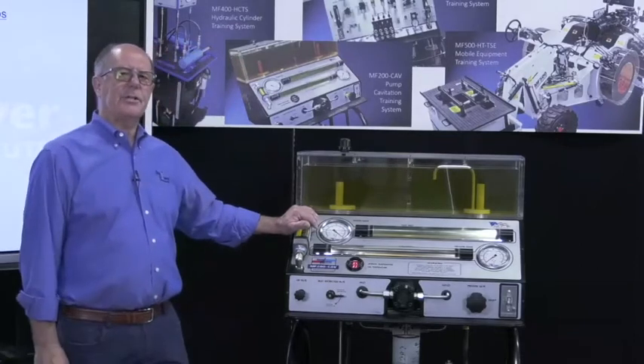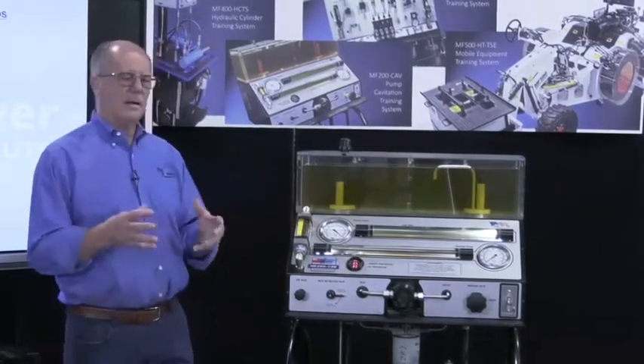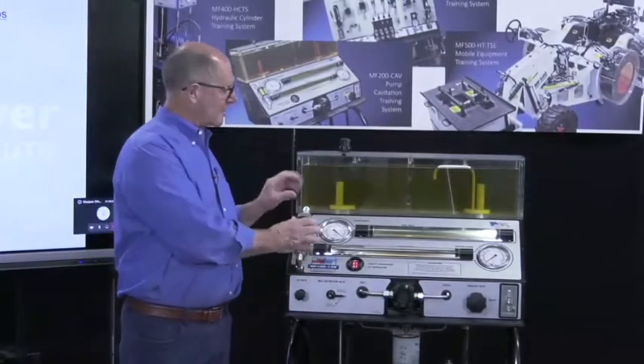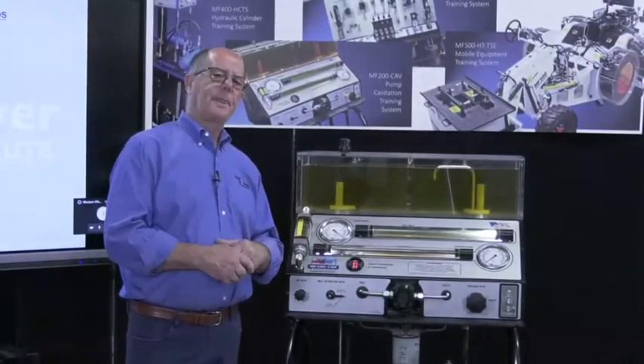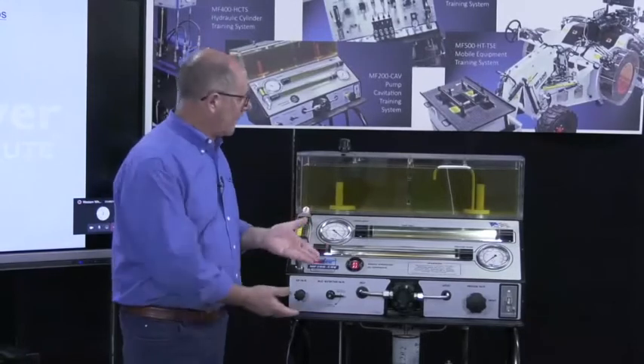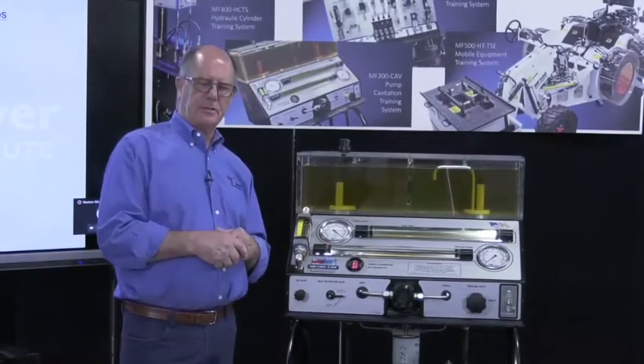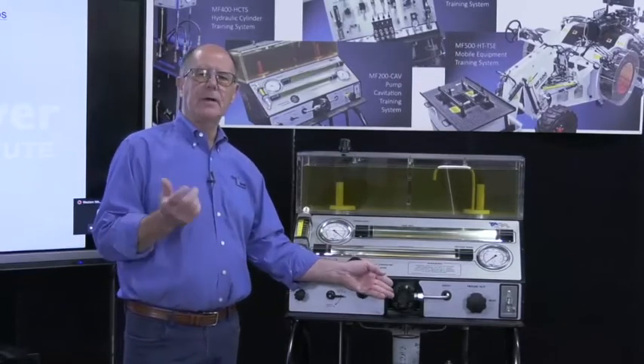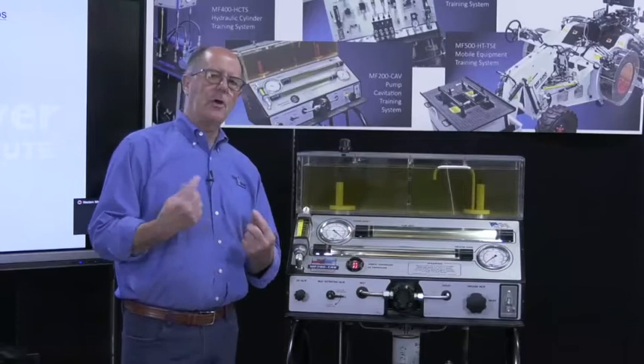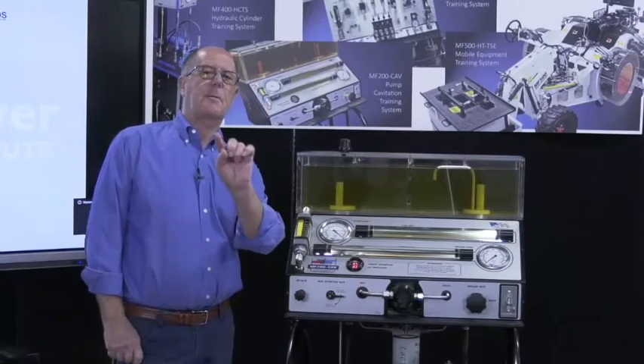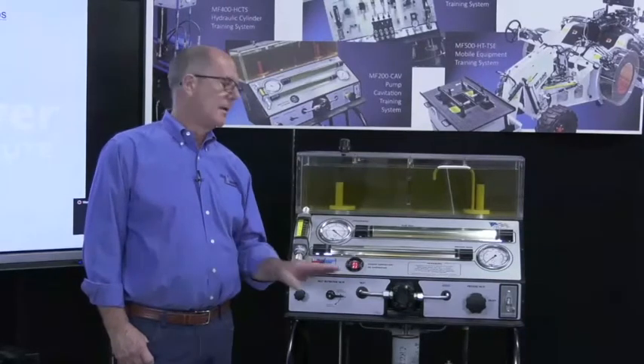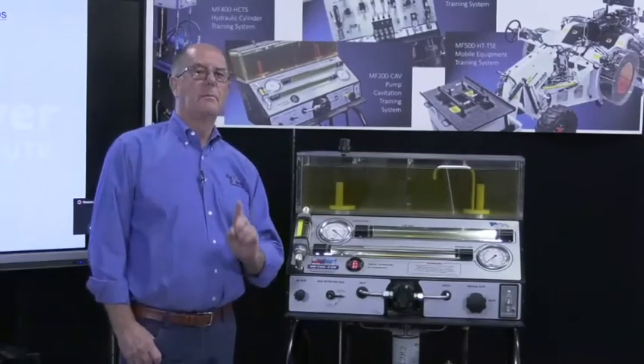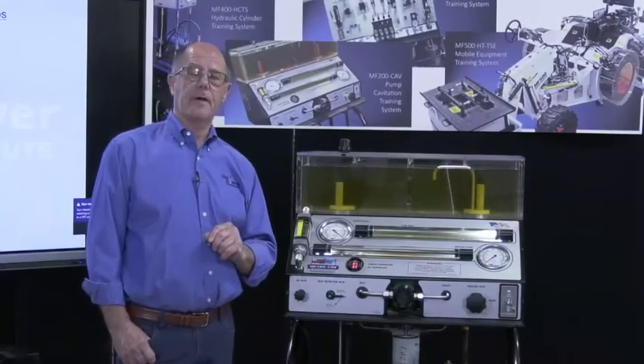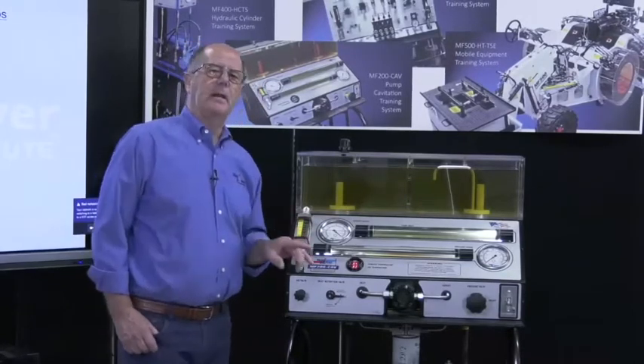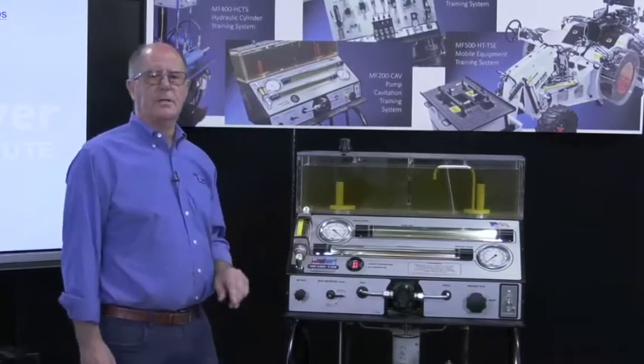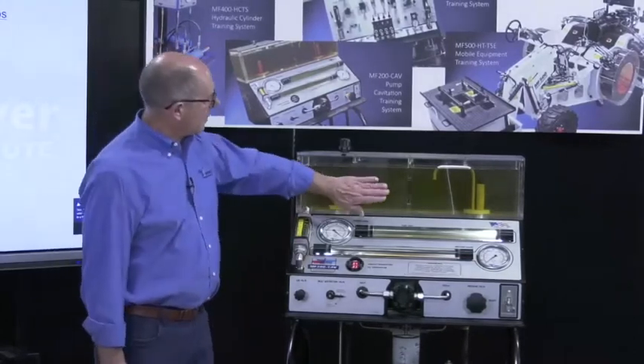To make cavitation easy to understand, let's say the workbook that comes with this particular trainer has 4 activities. Number one, we start it up and we get to know the patient. In other words, this is a gear pump, 1.8 gallons per minute. The first thing I'm going to show you when I start is how to establish the point of reference. We know by rule of thumb the maximum is 8 inches of mercury, but we will very quickly figure out the point of reference. Then, since we are monitoring everything here and the whole hydraulic system is transparent, we can see the oil.